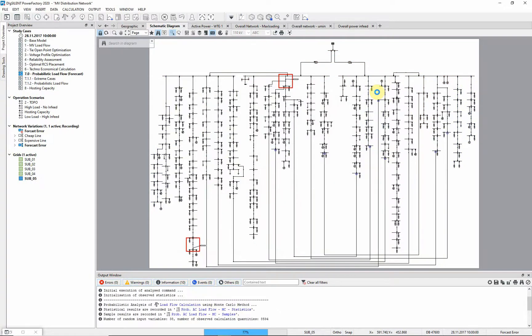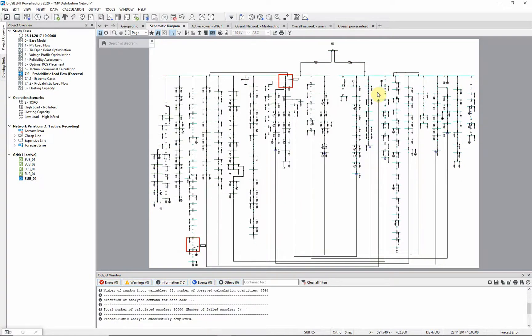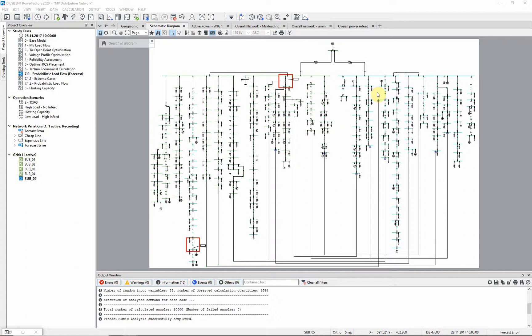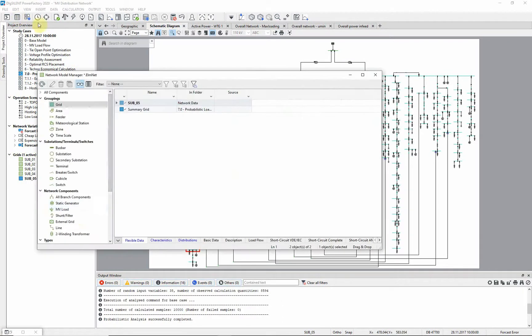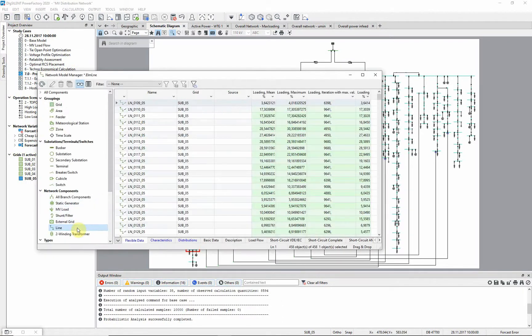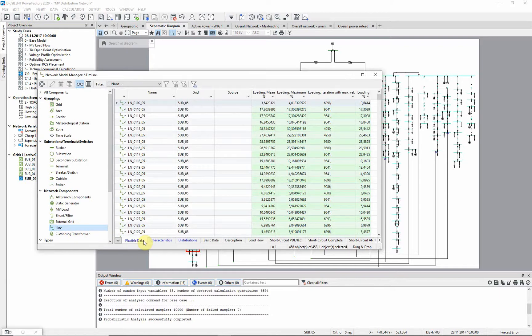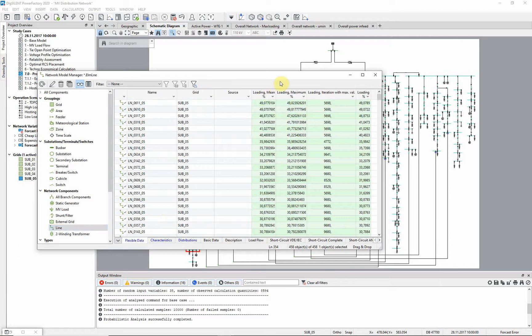Once the calculation has finished, the results can be analyzed. In our example, we are interested in finding the line with the highest average loading. Open the Network Model Manager and filter for lines. Go to the Flexible Data page, where some parameters have already been defined. Let us sort the lines by the mean of the loadings. This line has the highest loading.